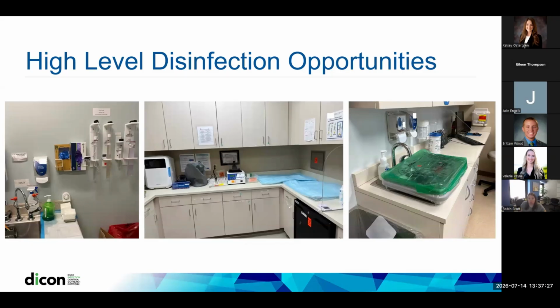So in that left picture, we had all kinds of things. We had hand soap that was above our reprocessing sink. Our eye wash station was connected to our dirty sink. There are so many items that are in the splash zone. In that green bottle was pre-mixed enzymatic detergent, but we had no idea what the dilution ratio was, and neither did any of the staff. There was no thermometer for measuring the temperature of the enzymatic detergent, which this particular enzymatic detergent required, and there were also no thermometers to check the temperature of the high-level disinfection solution, or they weren't logging those temperatures.